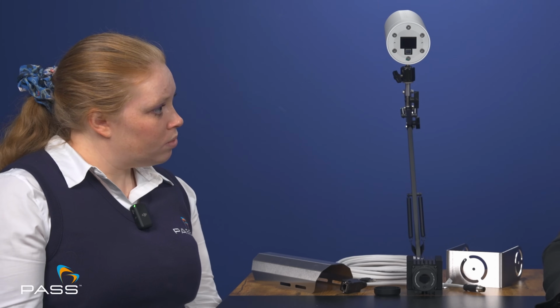It's not one spot meter that's looking at one spot. So I do think that that's one of the benefits that we see with why thermal imaging is the best benefactor in the market. So it's kind of the coverage, the safe distance, and presumably they can pick up heat earlier than a sprinkler system can. Correct. And these systems also integrate with a relay into a suppression system.